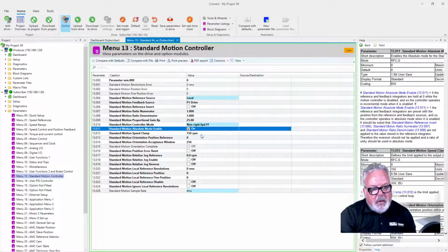All right, that's confusing. This is the maximum amount of speed command that the drive will use to correct for position error. So if it's lagging, it's going to add up to 150 RPM on top of the command to try to reduce following error. So that's not a speed limit, even though it says it is.